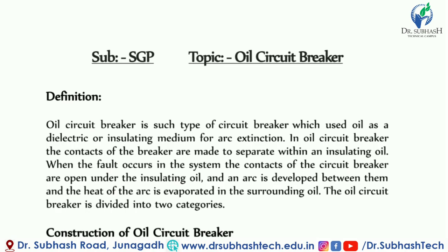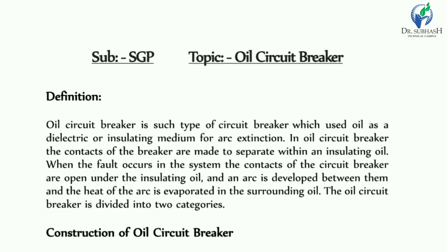An oil circuit breaker is a type of circuit breaker which uses oil as a dielectric or insulating medium for arc extinction. The arc extinction medium or dielectric insulating medium used is oil. The contacts of the breaker are made to separate within an insulating oil, and the arc is developed between them. The heat of the arc is evaporated in the surrounding oil.